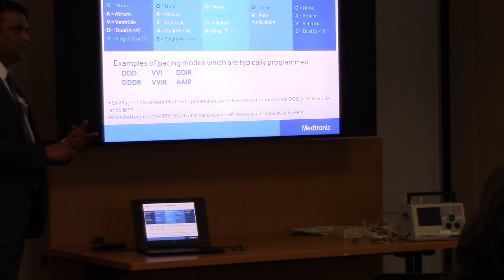Let's stick to this. So the first letter of the NBG code denotes the chamber that is going to be paced. So let's say you had an A there, which chamber would be paced? Anybody? If the first letter was an A, what chamber do you think would be paced? Atrium. If the first letter was a V, which chamber would be paced? And if it's D, what do you think would be paced? Both of them, right? The second letter of the NBG code is which chamber is being sensed.